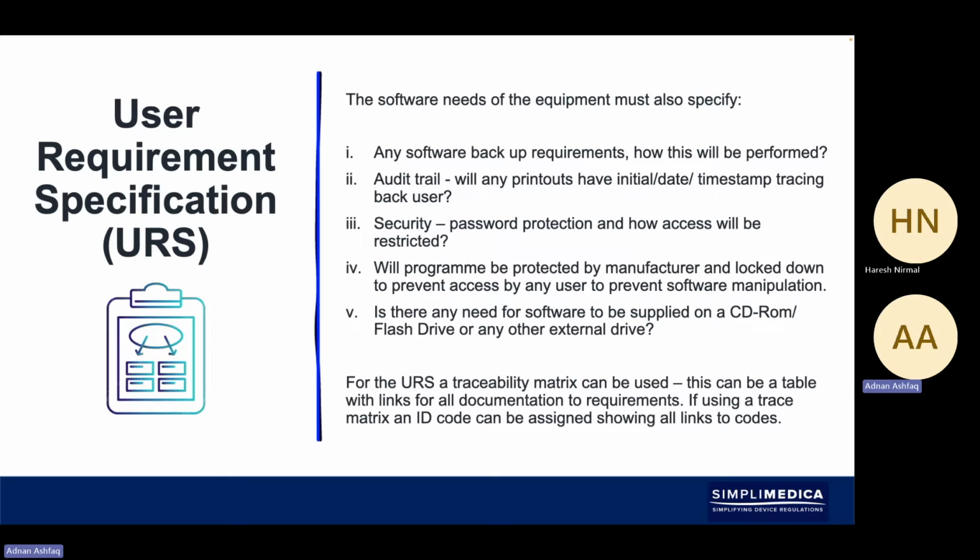So in terms of software needs, the equipment must also then look at any software backup requirements. How will this be performed? Any audit trail? Will any printouts have any initial, date, timestamp tracing back to the user? Security: how will this be password protected? How will access be restricted? Will the program be protected by the manufacturer and locked down to prevent access by any user, to prevent software manipulation? Is there any need for software to be supplied on an external support, or will it just be done by cloud or on an intranet system, etc.? These are obviously various factors for consideration.